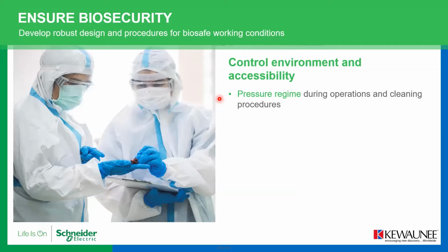The first thing is maintaining the pressure regime, which is very important - that means your operating and cleaning procedures in terms of air changes, humidity level, or temperature minimum requirements. Yes, these are very important to maintain from an environmental point of view.